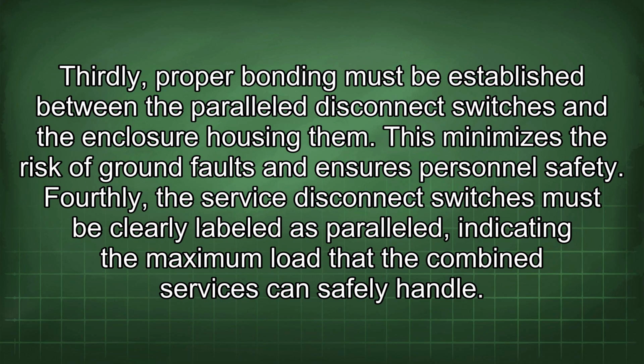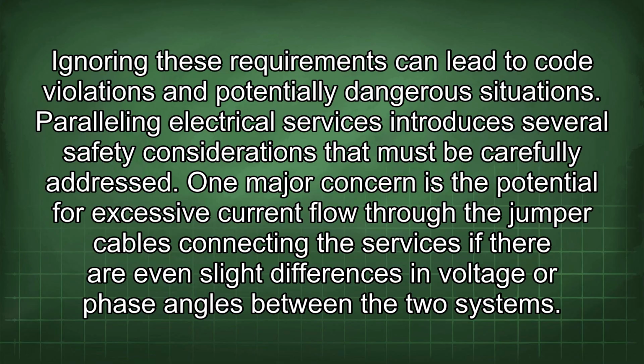Thirdly, proper bonding must be established between the parallel disconnect switches and the enclosure housing them. This minimizes the risk of ground faults and ensures personnel safety. Fourthly, the service disconnect switches must be clearly labeled as paralleled, indicating the maximum load that the combined services can safely handle. Ignoring these requirements can lead to code violations and potentially dangerous situations.